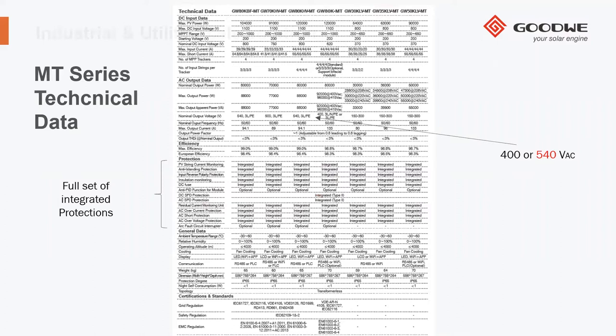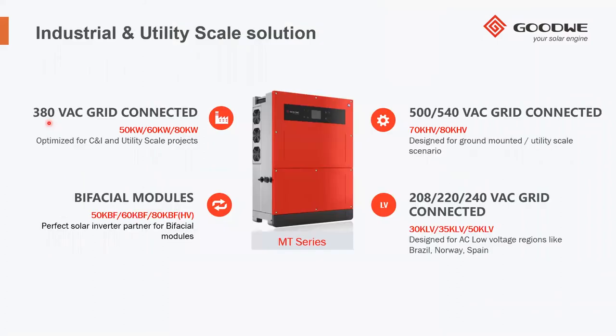As I mentioned, you can have an exit at 380 volt AC, and this is what we standard design for a commercial, industrial, a small utility scale project. You can have an exit at 500 or 540 volt AC, typically for ground mounted and big utility scale project. You have the version which are the BF for bifacial modules, so can be already adapted for the use of bifacial modules. And for special countries like Brazil, Norway, and Spain, we have also the version with the low voltage, we call low voltage, 30, 35K and the 50K version.